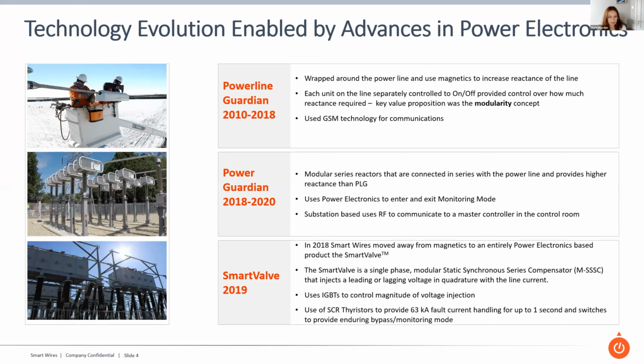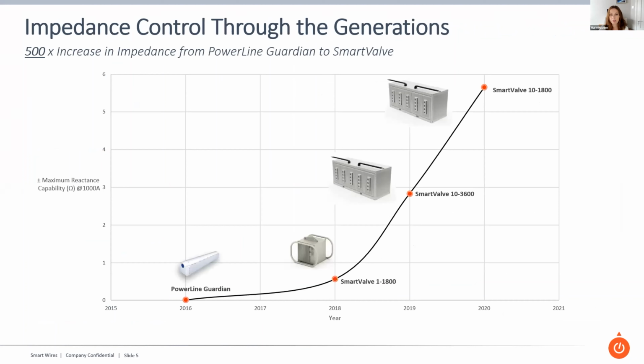The electronics which enable all of this is a combination of voltage source conversion technology, and I'm sure you'll hear more about VSC technology in the subsequent presentations. It forms the basis of some of the HVDC interconnectors. And that is made up of IGBTs, transistors, which control the amount of voltage we inject into the line. So I'll show a single line diagram to try and talk through that a little bit more. Just one thing I want to say is just the scale of the increase in impedance control we have achieved over the last 5 years with the technology.